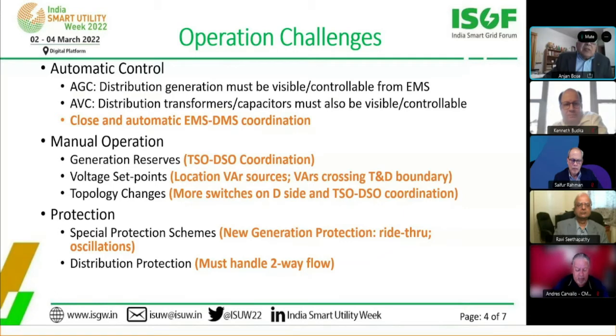We're seeing special protection schemes to do ride-throughs. We're seeing wind farms causing oscillations, which will require new protection schemes. And on distribution protection, this is where this two-way flow comes in. This is the whole distribution protection with handling two-way flow and large amounts of generation on the distribution system, requiring new ways of coordinating this protection system.